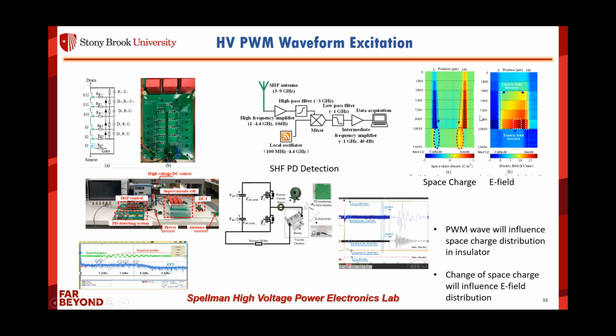There's also another observation we noticed. Basically, the space charge during this kind of partial discharge event—your PWM signature will influence the space charge. And if you change the space charge in your insulator, you'll see a difference in the E field distribution, making the E field distribution in the insulator totally different.